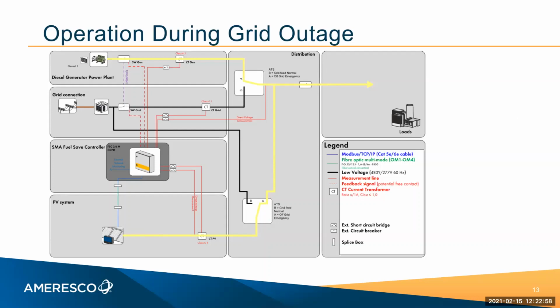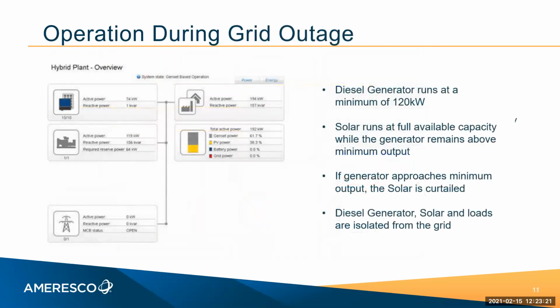So we had to install the bottom ATS to allow this system to be transitioned from a front of the meter system to a behind the meter system. And then it was connected to the loads and to the diesel generator, completely disconnected from the grid. And now, George, if you could just go back 2 slides. And this is an example of what would be happening during a grid outage.